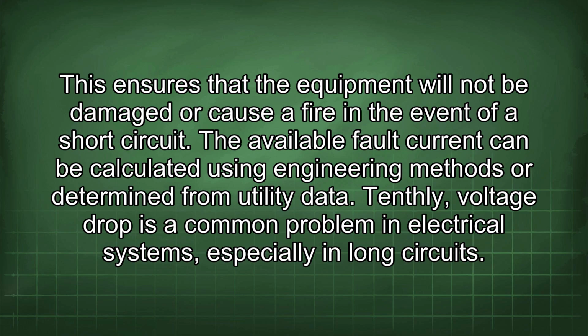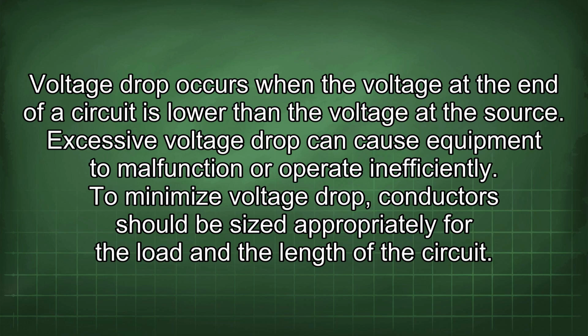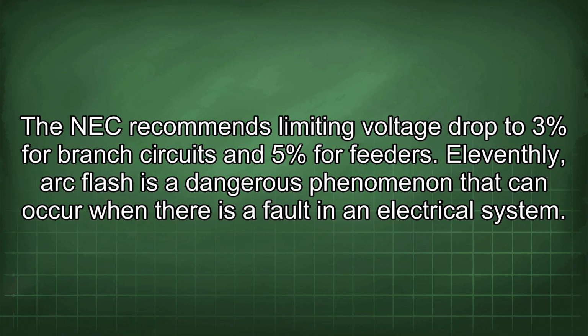Tenthly, voltage drop is a common problem in electrical systems, especially in long circuits. Voltage drop occurs when the voltage at the end of a circuit is lower than the voltage at the source. Excessive voltage drop can cause equipment to malfunction or operate inefficiently. To minimize voltage drop, conductors should be sized appropriately for the load and the length of the circuit. The NEC recommends limiting voltage drop to 3% for branch circuits and 5% for feeders.